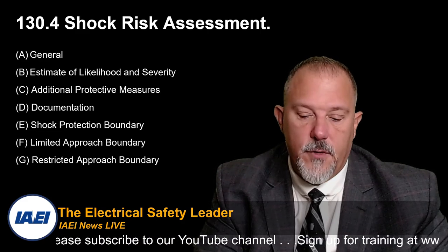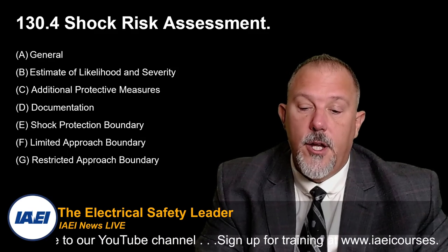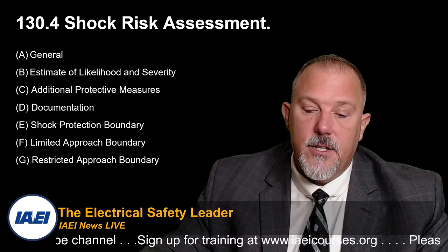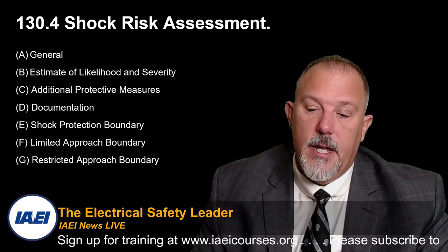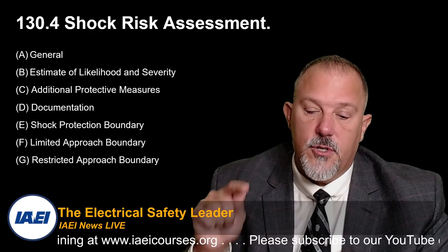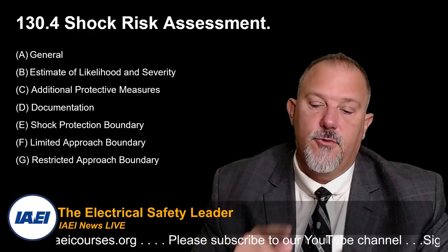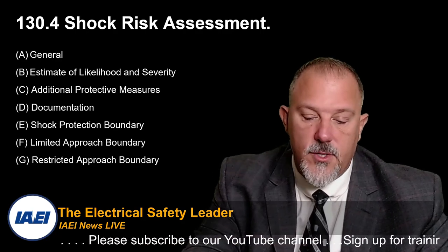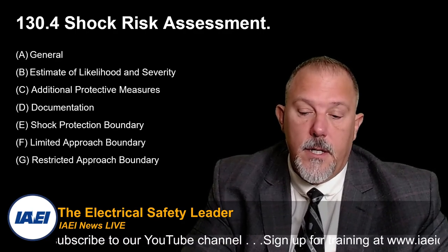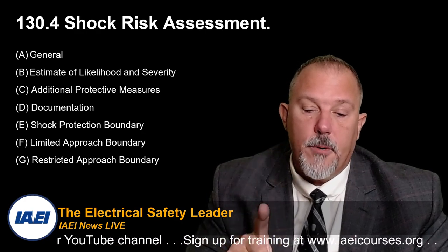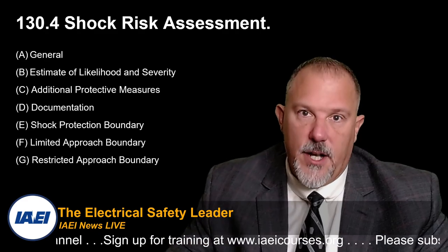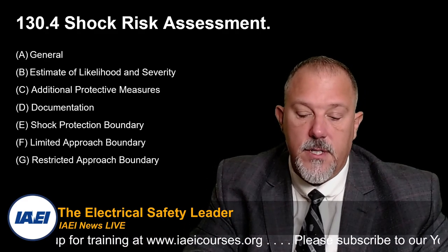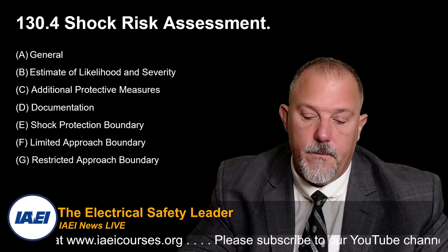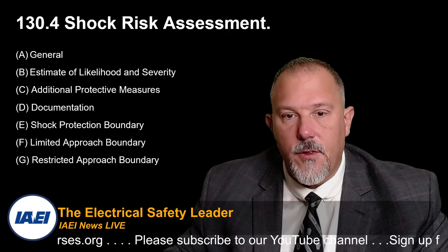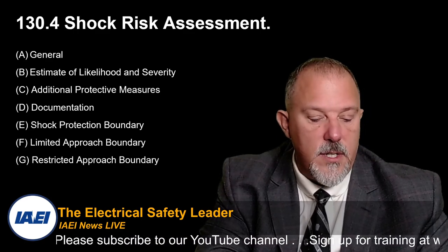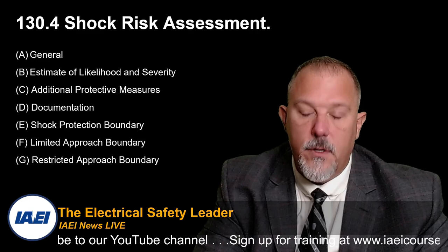And then they'll tell us that's our 3 foot 6. Then you have a restricted approach boundary. No qualified person shall approach or take any conductive object closer to exposed energized electrical conductors or circuit parts than the restricted approach boundary. And for that 480 volt circuit, that is 1 foot. It says, no qualified person shall approach or take any conductive object closer than, so for a 480 volt system, 1 foot, but it varies based upon voltage. And that boundary gets further back. So if you're into say 4160, you're back at 2 foot 2 inches.